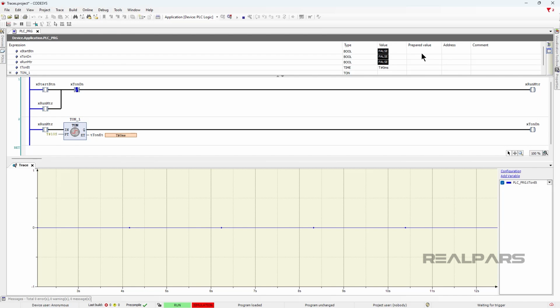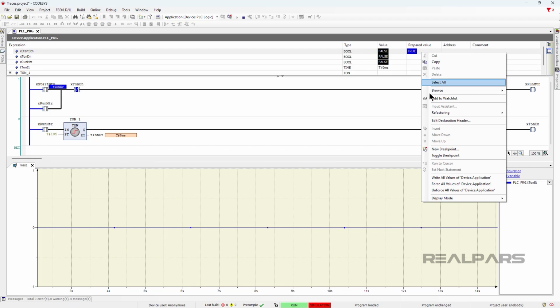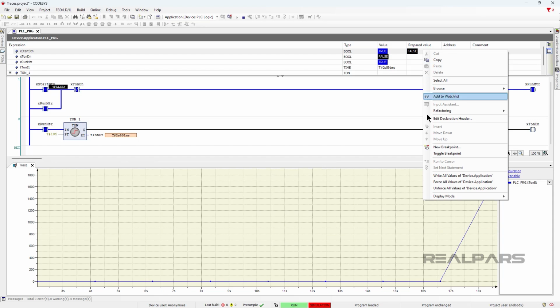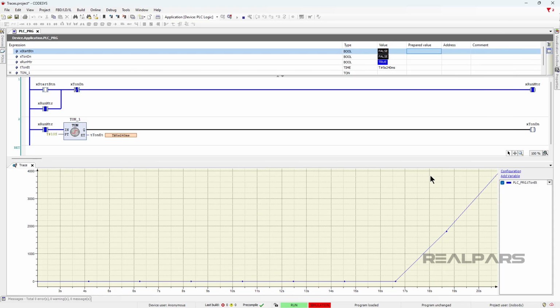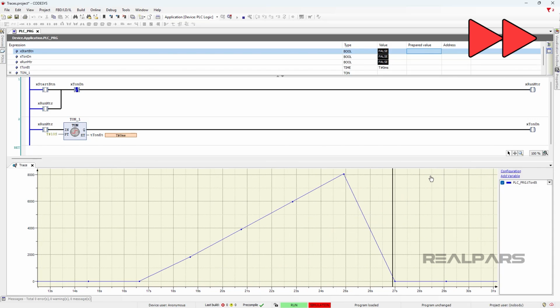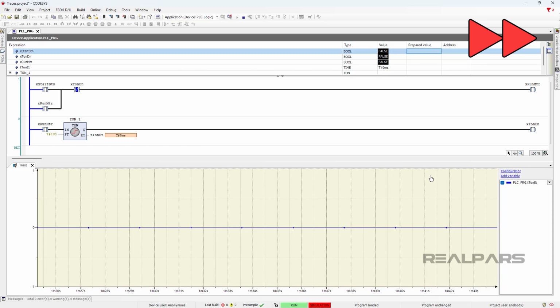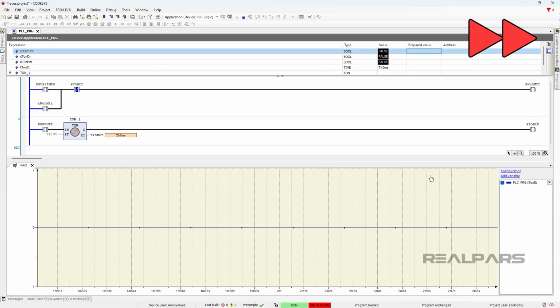Once the trace has been downloaded, I modify the value of the variable xStartBTN to true, and the trace starts collecting data. When the value of xRunMTR becomes false, the trace trigger is activated, so the trace collects the defined number of post-trigger samples and then halts.